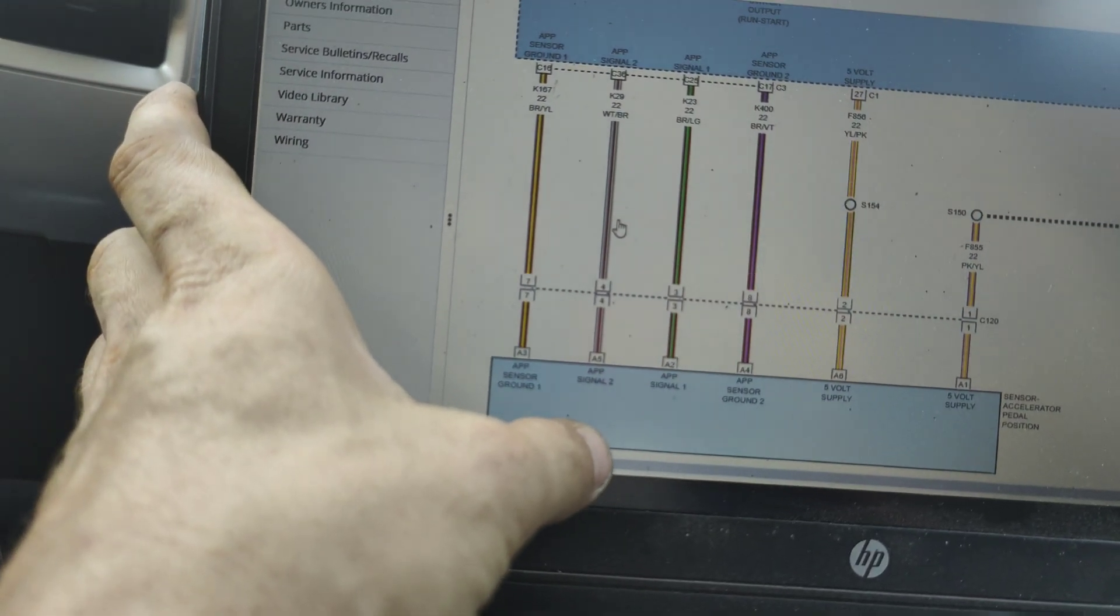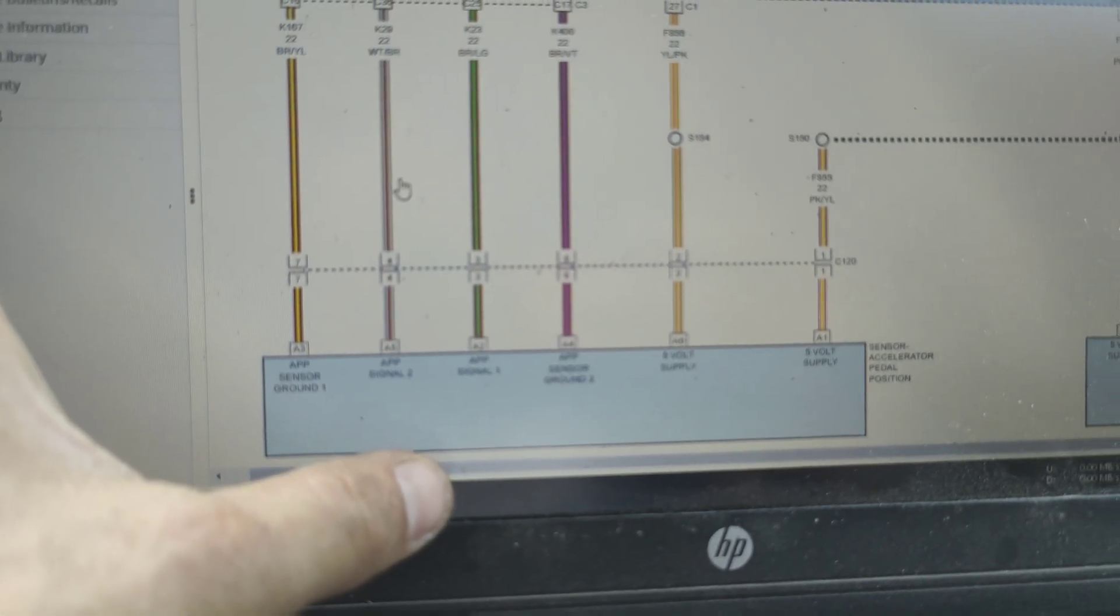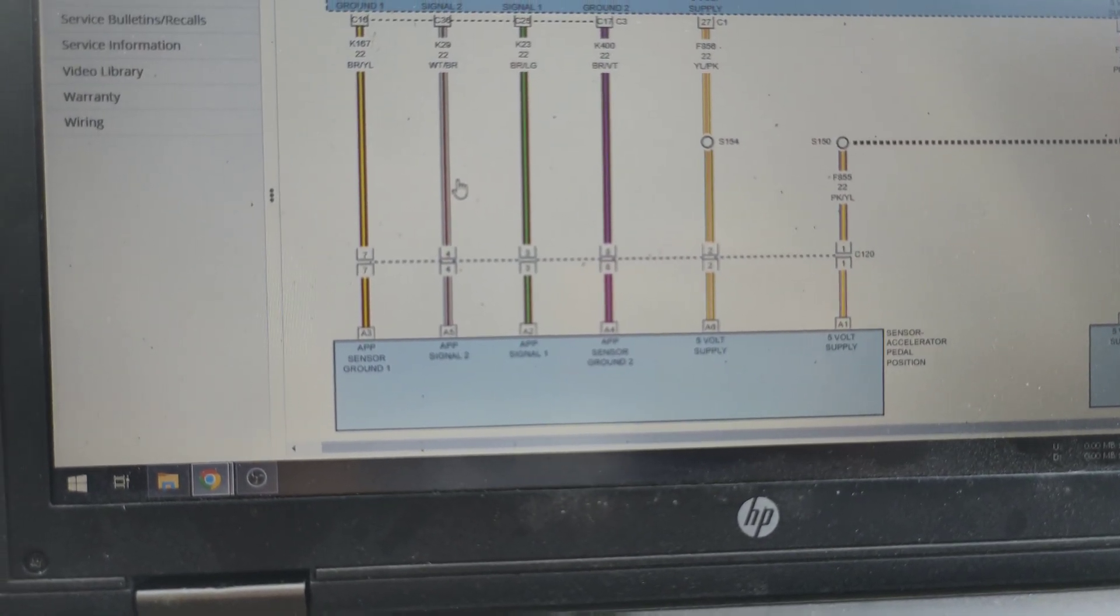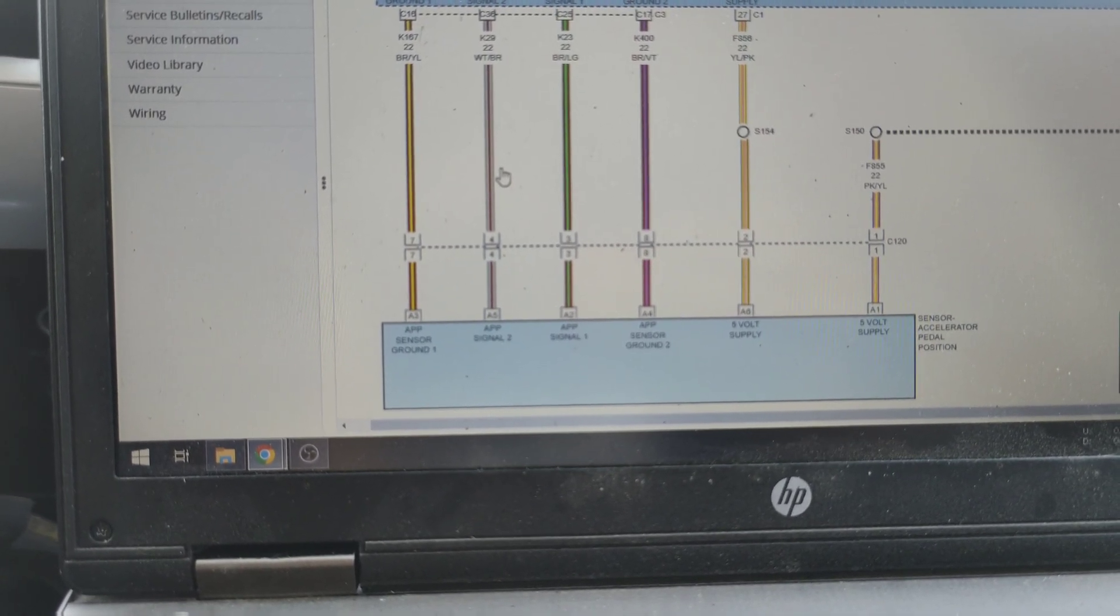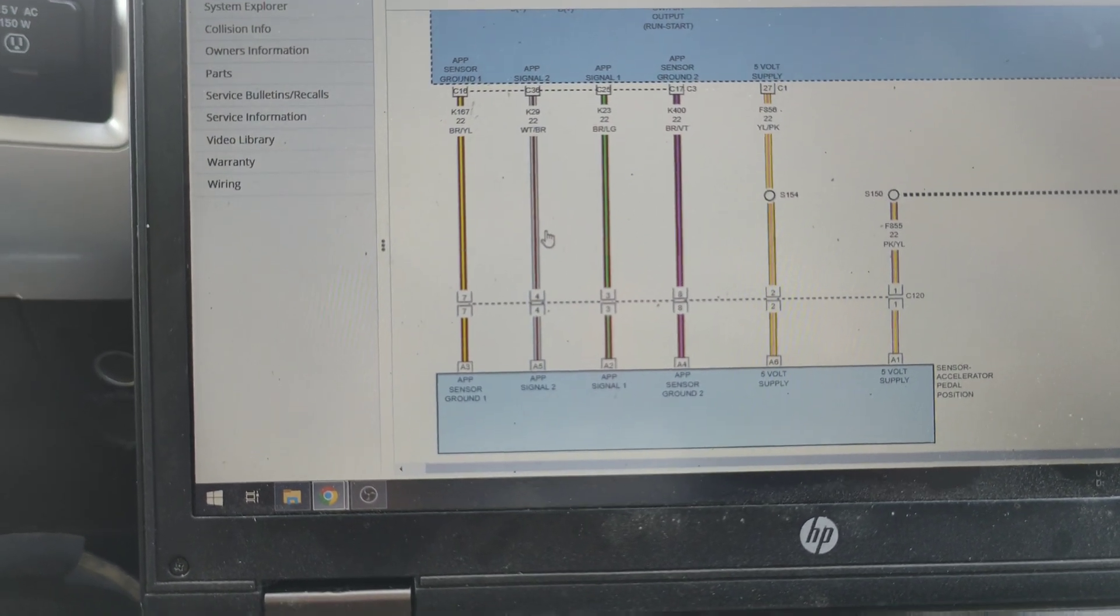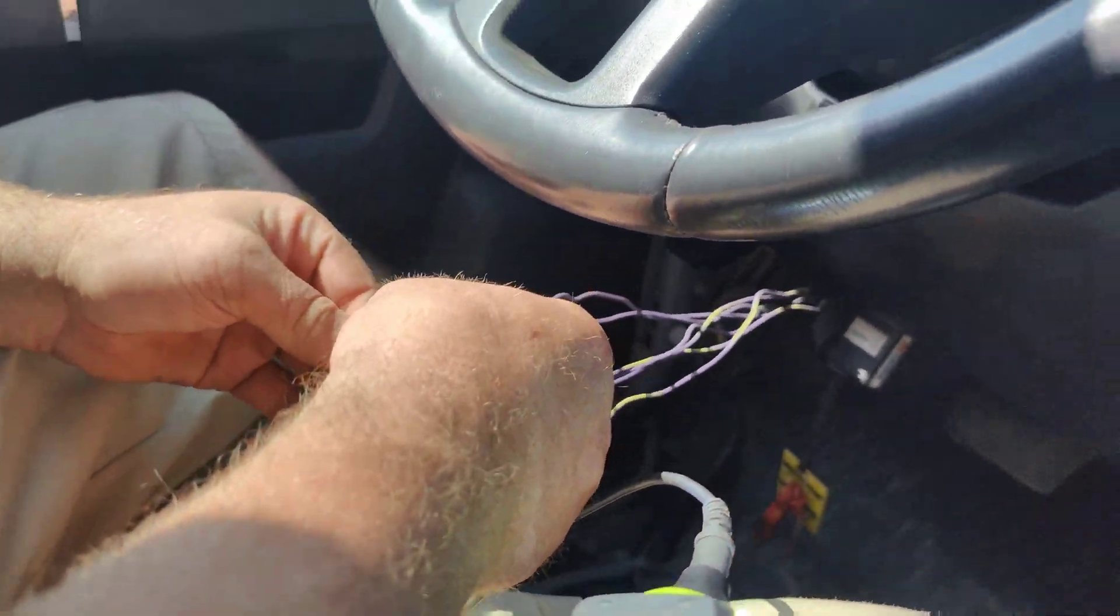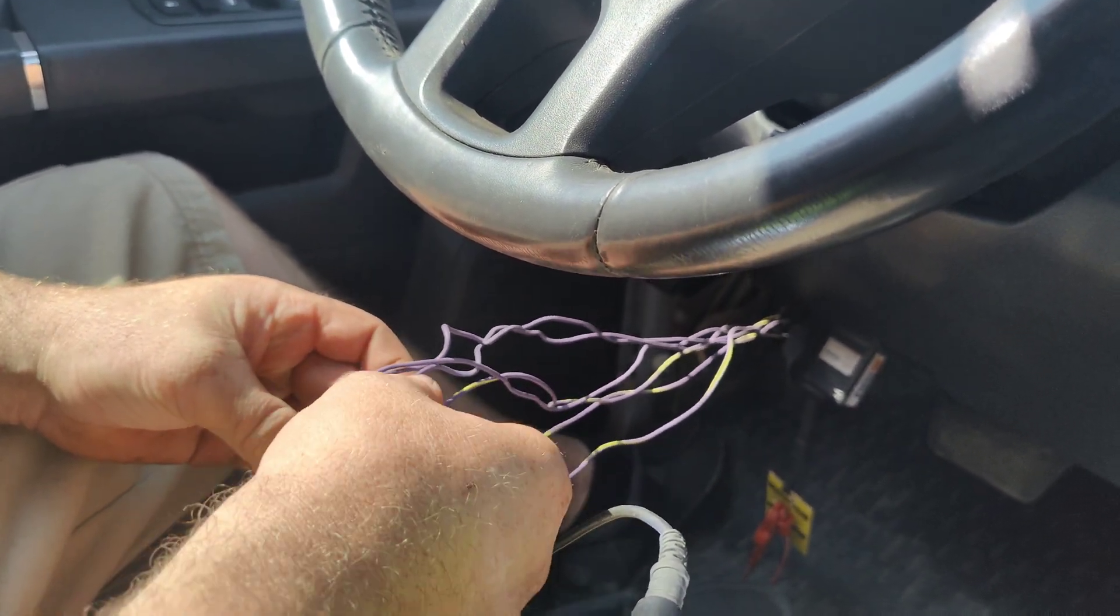This is what our diagram shows. Our signals are supposed to be pin 2 and 5. Signals should be pin 2 and 5. So I have signal on pins 2 and 3. So what we're going to do here is we're going to take pin 3 and we're going to move it to pin 5. Okay? That's what... your grounds are supposed to be 3 and 4. Yep. So we're going to take this solid purple wire, which is pin 3, this one right here. We're going to move that pin to pin 5. And we might correct our problem. Should I get a de-pinning tool or are you... Because we had that cover off remember? Yeah I already had to take the cover back off. I'll grab a tool.